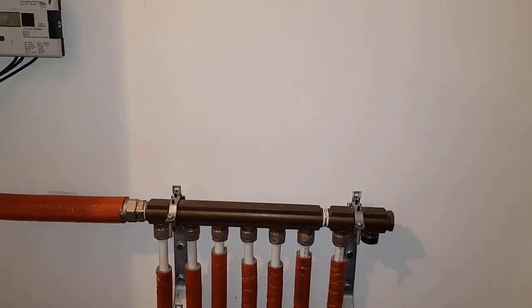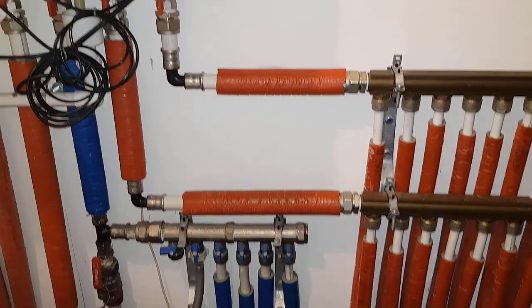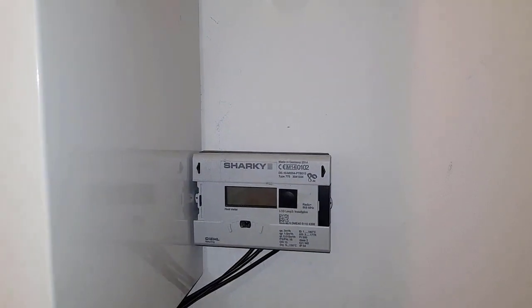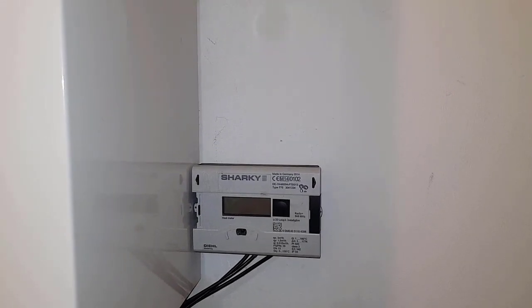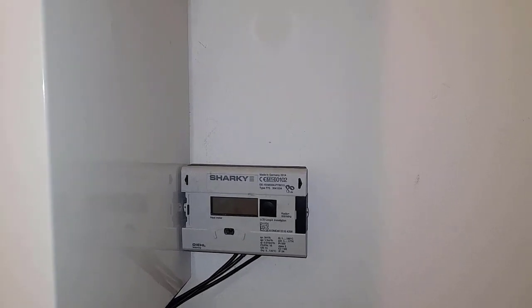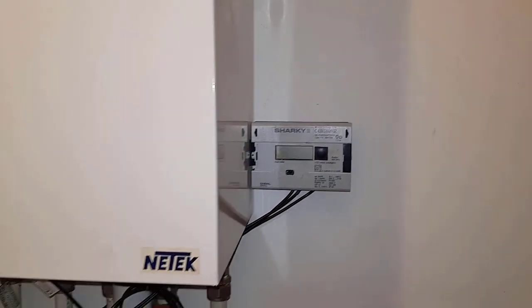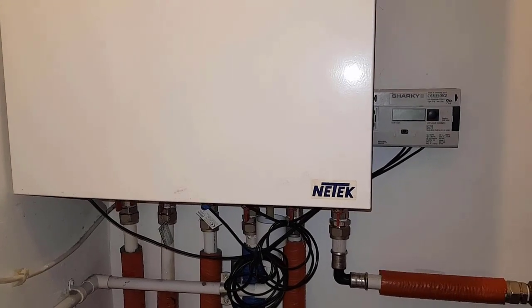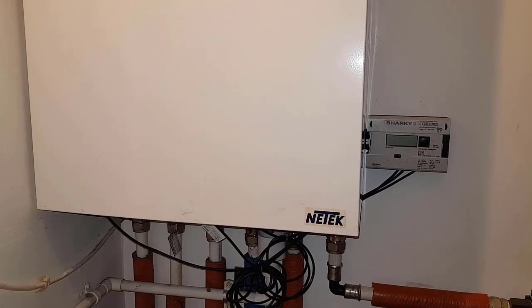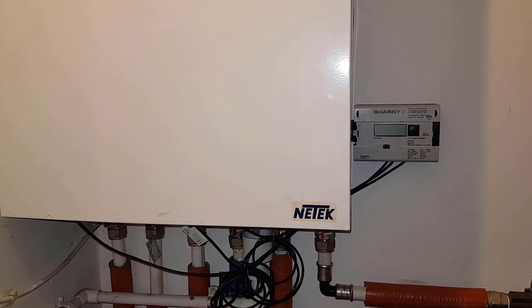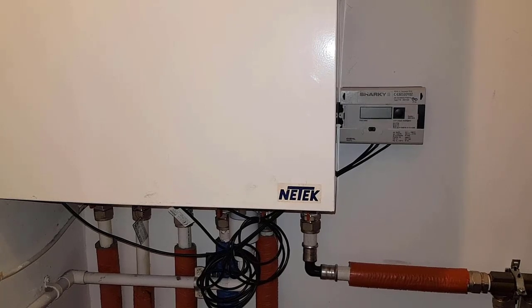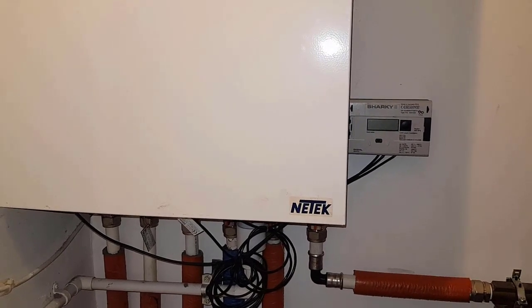So you can see this manifold, that's a flow, that's return, and this unit here measures, it's like a meter, so it charges the customer for heat rather than using gas and electric. That's what that does. So this boiler is being heated by one big communal boiler. The flow and return from that main boiler goes to this unit, and it's got a couple of heat exchangers inside which we're going to look at. Once the main power source goes to the heat exchanger, that gives heat to the heating, and a separate one for the hot water. So we're going to look inside and find out.